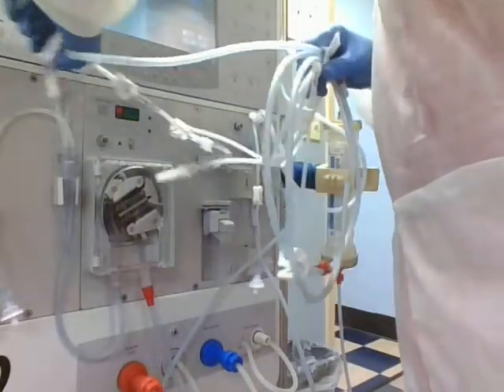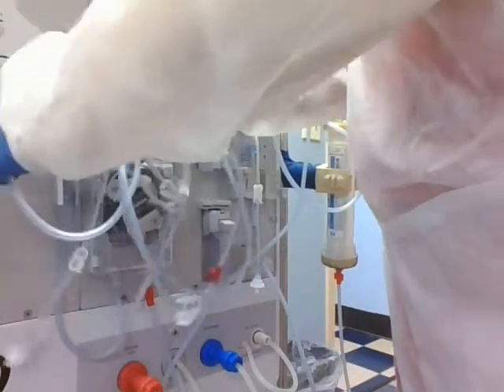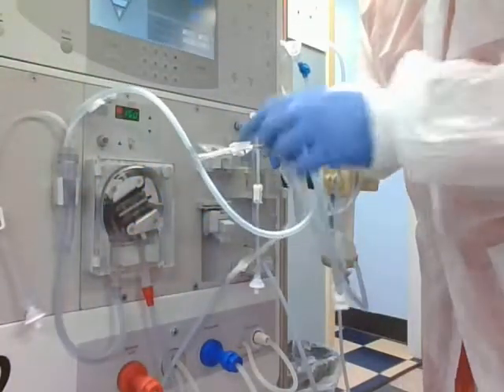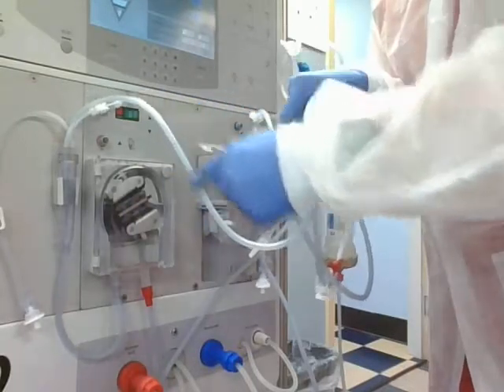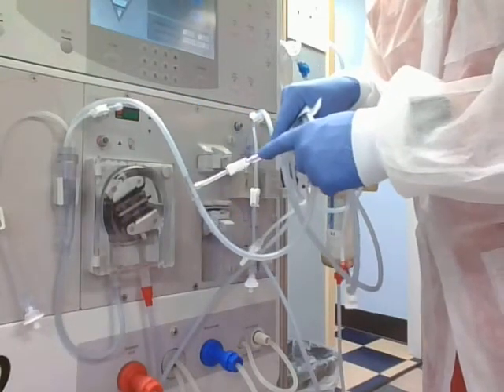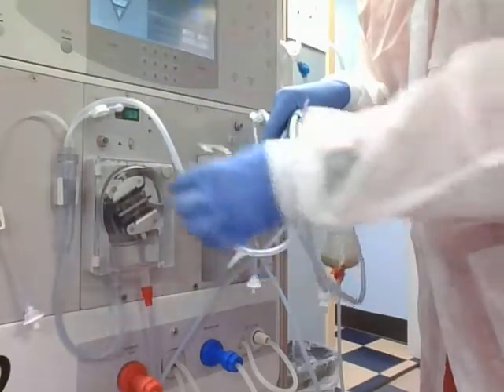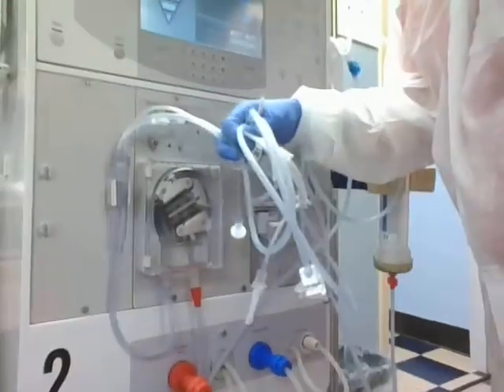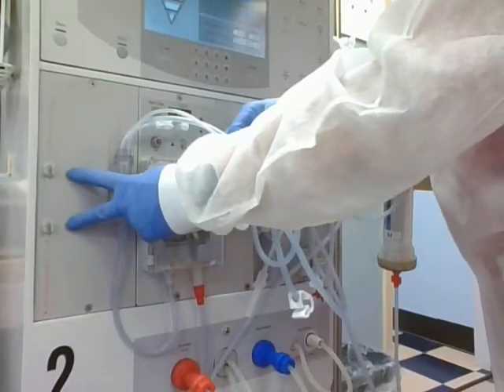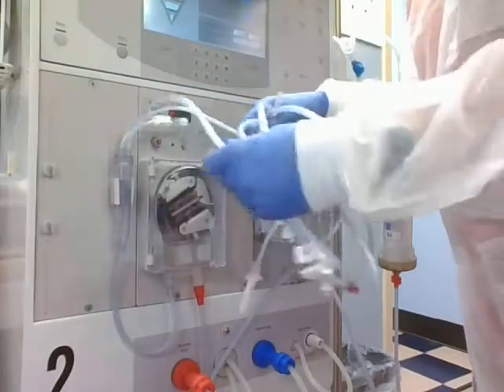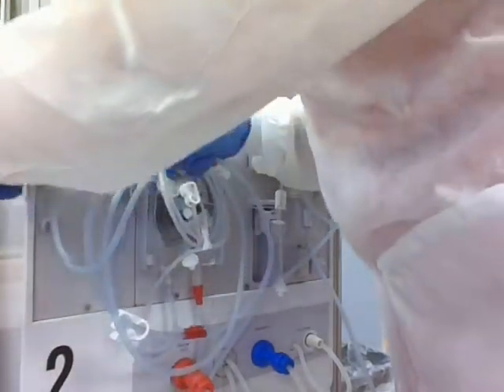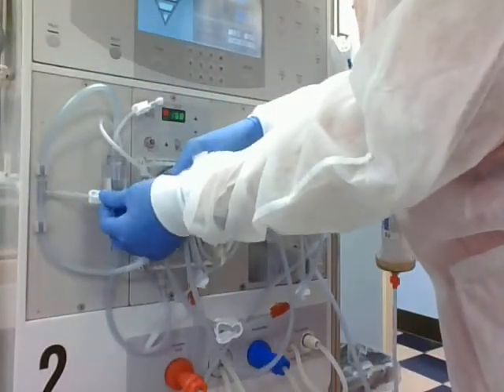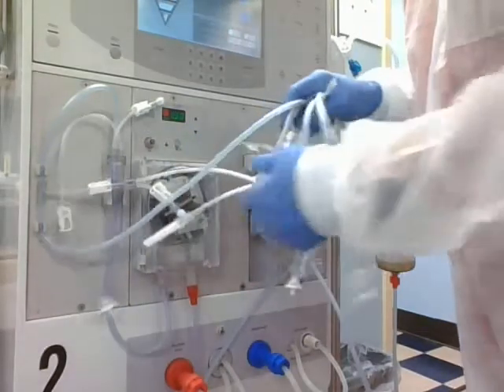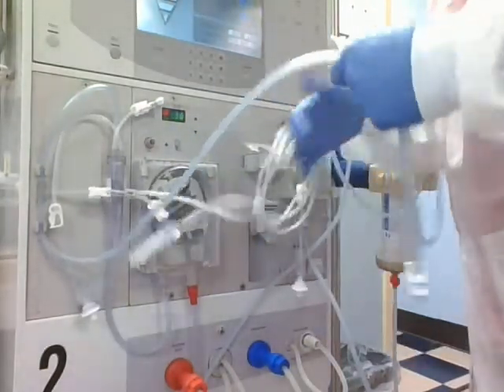So this part comes over to the module compartment. I like to call this the T box. Notice how it makes a T right here with my saline line. I call it the T box just so it's a visual. The actual name of the piece of equipment is called the module compartment. That's these two connectors right here where we set your saline module. You put your saline line directly between the two. All right, that line you leave open because we need our saline. That's how we're going to prime our machine.